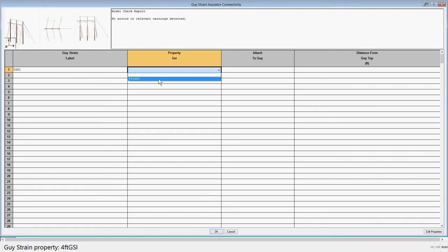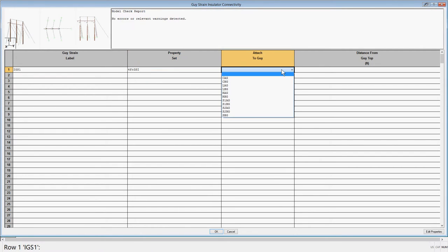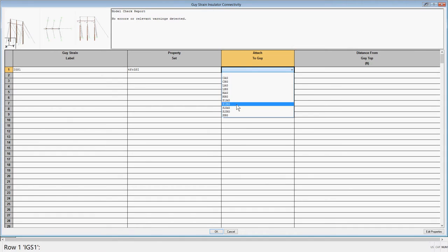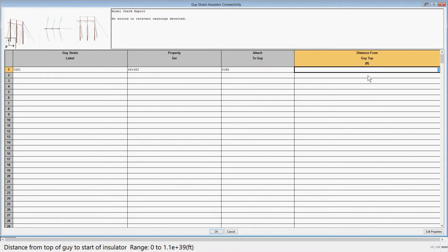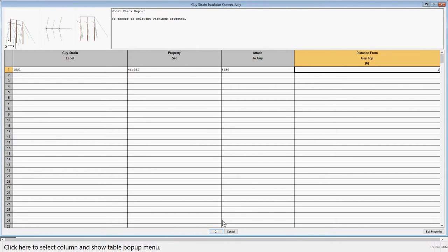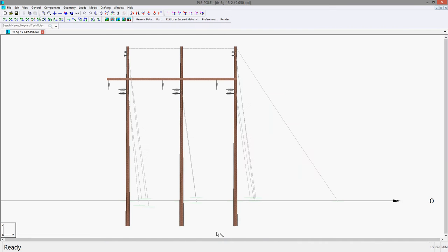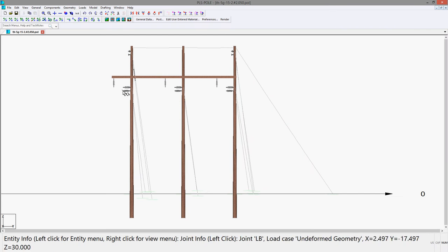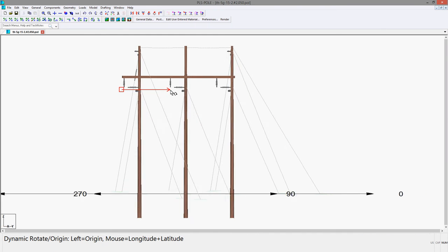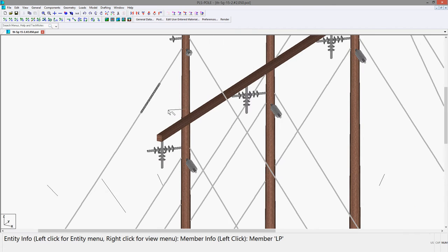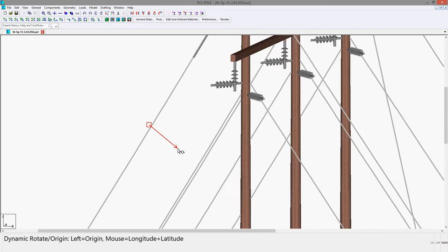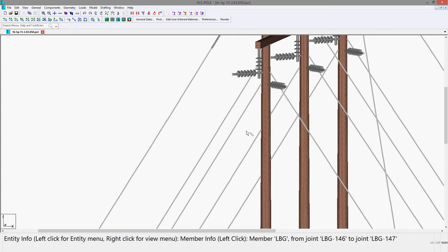Then we'll pick a down guy we wish to attach to, which is the S1BG. The last column is the distance down the guy where we want to attach the guy strain insulator. We'll start with 5 feet and see if this meets our requirements. Then hit OK and we can see that the guy strain rendered in the model does not appear to be in the location where we want to provide clearance to the conductors.